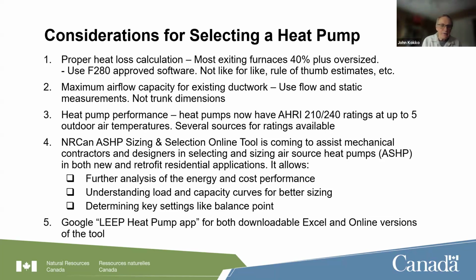When we get into selecting heat pumps themselves, there are a couple of things we want to be aware of. One is using proper F280 approved software. F280 is the Canadian standard for doing a heat loss on a house. And we want to be really careful not to use a like for like, trying to size the heat pump for what the existing furnace is if it is a retrofit, because existing furnaces can be up to 40% and even more oversized for houses. The example I showed, I think it was like 35% oversized, was the furnace that was in there. So doing a like for like exchange is not a very good strategy.